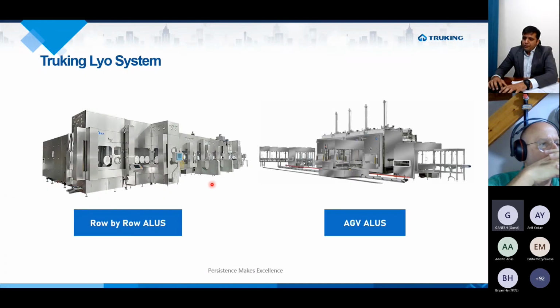Under Industry 4.0, as we said, we can transfer the containers under varied levels of containment, starting from OEB level 3 to OEB level 5, which is an isolator for cytotoxic product, talking about ADC medicine precisely. It can automatically load the freeze dryer with robotic loading of the containers inside, and offloading is also done automatically by robot, or you can have an automatic guided vehicle. Particularly in this video, you have multiple lyophilizers 1, 2, 3, and this automatic guided vehicle is transporting the vials from this area to this particular lyophilizer loading. This cart can also be incorporated with open RABS at OEB level 3 containment. If more strictness is required, then we have to go for a fixed type of solution at this point.